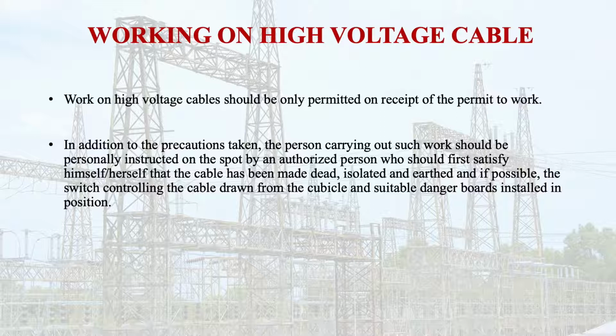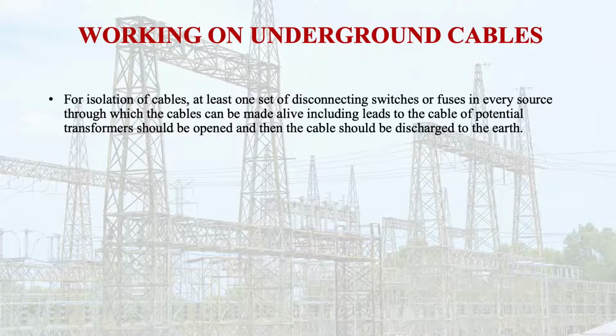Now working on underground cables. What safety precautions are involved in this case? For isolation of cables, at least one set of disconnecting switches or fuses in every source through which the cable can be made alive, including leads to the cable of potential transformers, should be opened. That means the leads of the cable of the potential transformer also, if there, should be opened, and then the cable should be discharged to the earth.